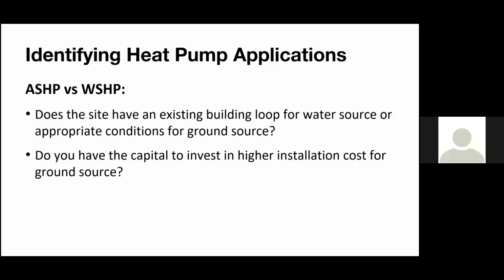If there is no infrastructure, just bricks and mortar, if it's a completely new building, then a lot of people looking to go all electric will often try to compare air source versus ground source. And generally, the air source heat pump is going to be your lower capital cost up front, as I already mentioned earlier. There's much less infrastructure: the condensers outdoors, which I already touched on, and indoor units in the building, whereas the ground source heat pump needs that entire hydronic infrastructure, all the water and loops, which tend to be higher capital cost. I think there are companies out there that actually fund and finance that portion in the ground source heat pump world as well.